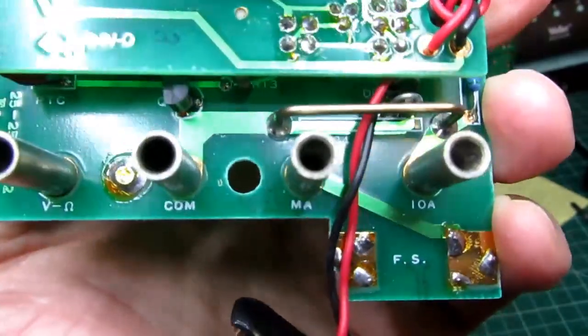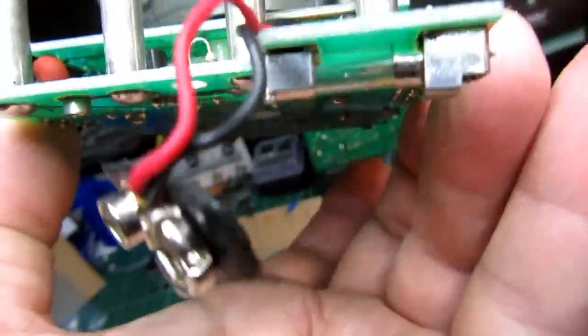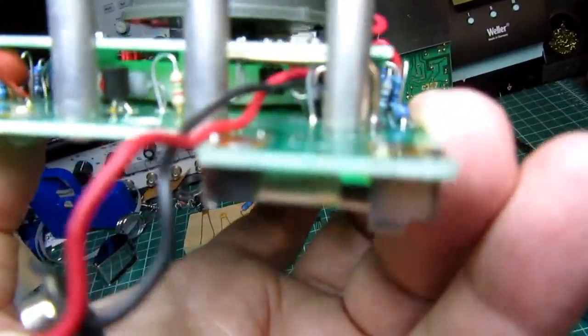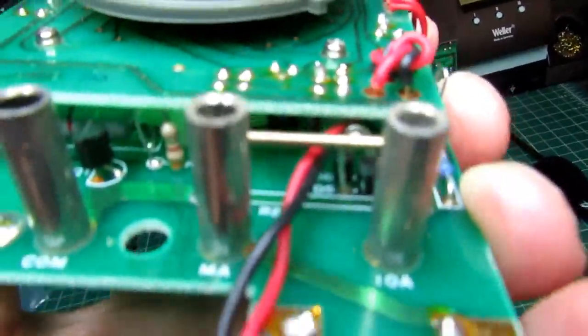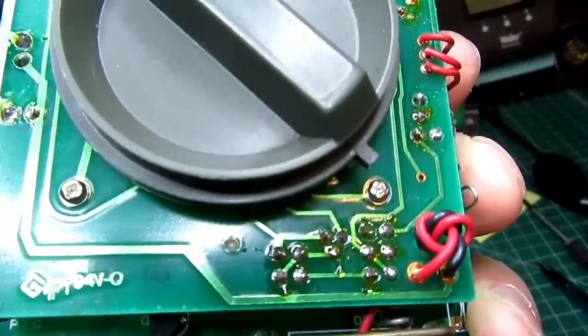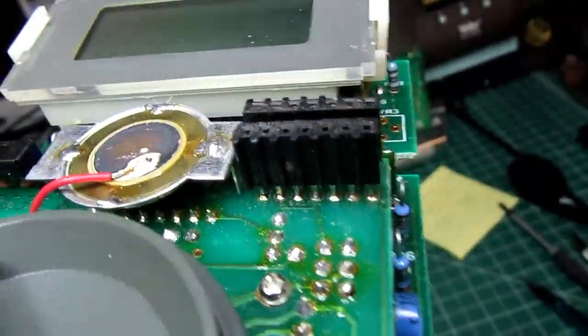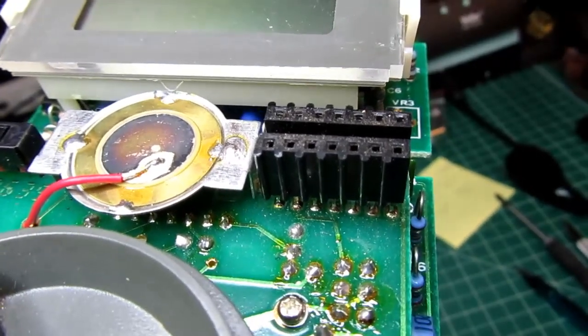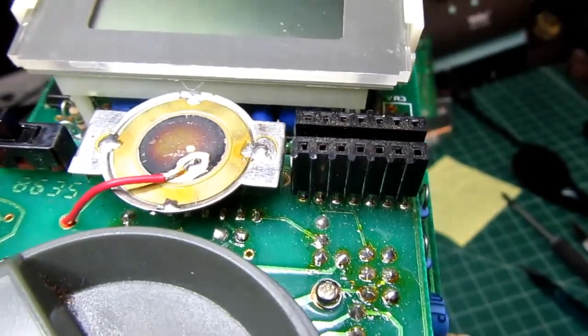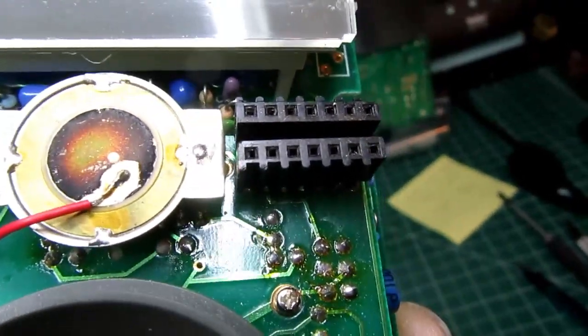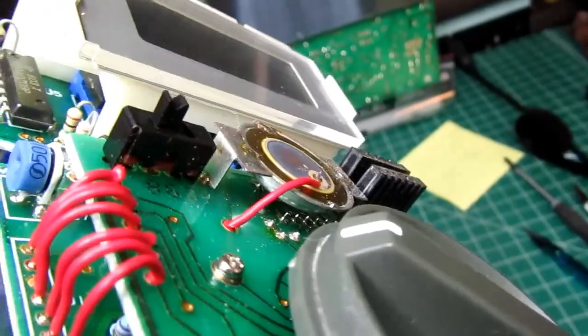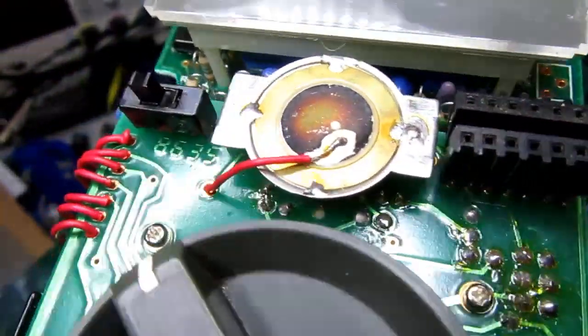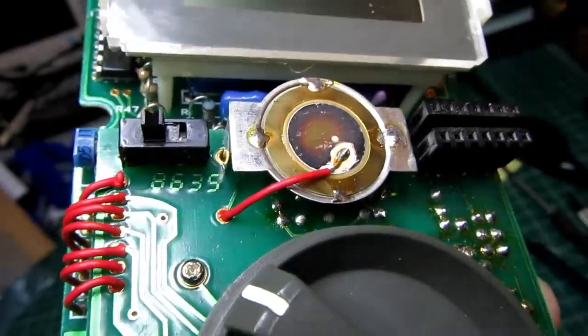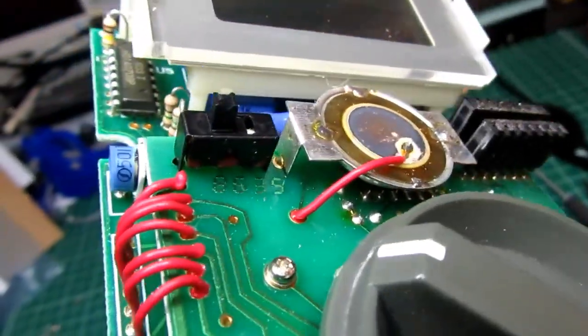Anyway, so what we have here is the 4 terminal posts and the fuse that's only used on the lower current or the milliamp ranges. It's not used for voltage or ohms or anything. It's just for the lower current ranges. And then there are a couple of socket headers which are used for the capacitor and transistor features of this meter, where you can plug their leads into those. There's the little piezoelectric transducer that acts as the beeper in the continuity mode.